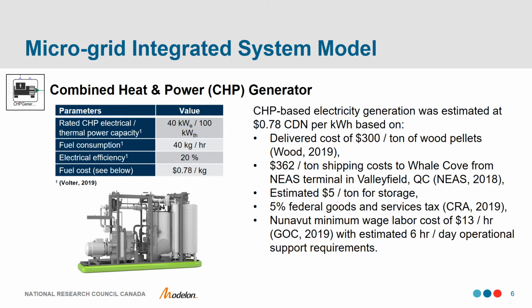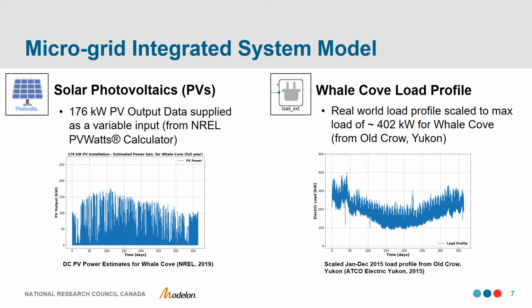Next, we have the combined heat and power, or CHP, generator model. The CHP generator was assumed to have a fixed power output of 40 kilowatts of electrical power and an estimated cost of $0.78 Canadian per kilowatt hour, based on delivery, shipping, storage, tax, and labor costs. The PV output power was supplied as a variable input to the integrated system model, with data taken from NREL's PV watts calculator. Based on a fixed power output from the CHP generator and an overall microgrid capacity of 216 kilowatts for renewables, the PV system size was set at 176 kilowatts. The data for Whale Cove, based on multi-year weather data averages, is shown in the chart on the left. In addition, in the absence of load data collected directly from Whale Cove, load data from Old Crow, a representative northern community in the Yukon, was used and scaled to maintain the maximum load constraint of 402 kilowatts for Whale Cove. This data is shown in the chart on the right.